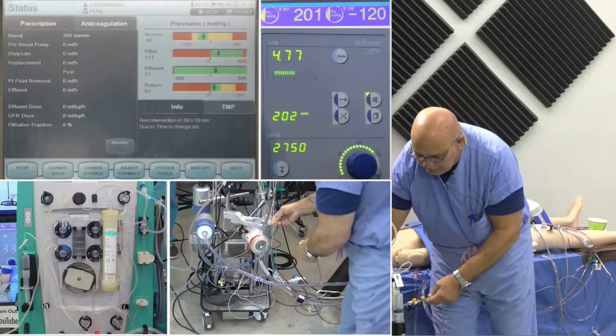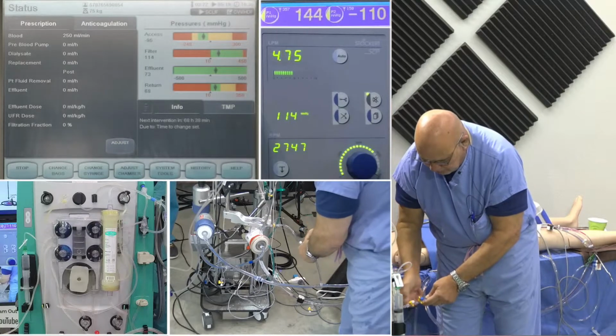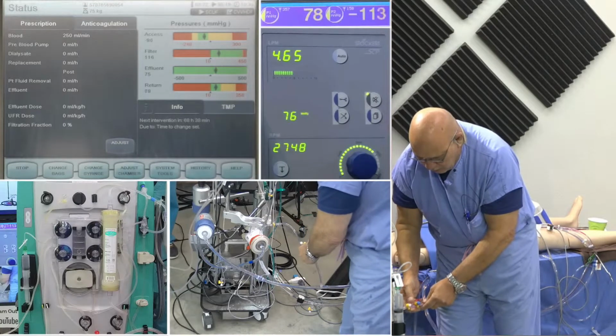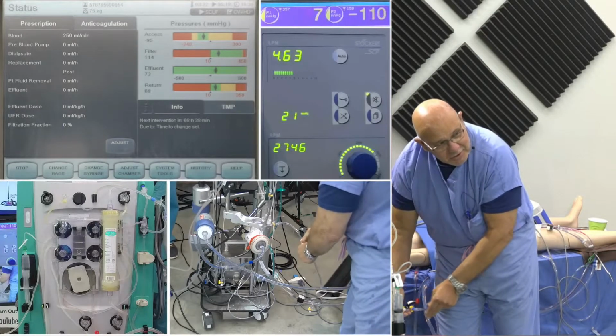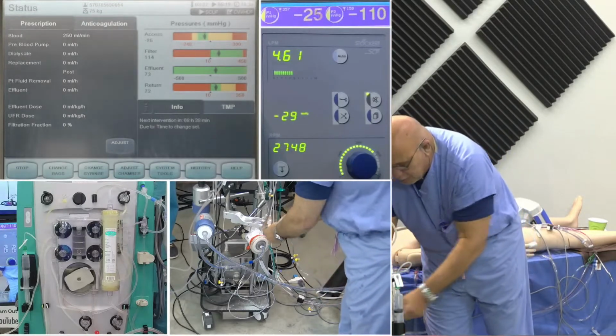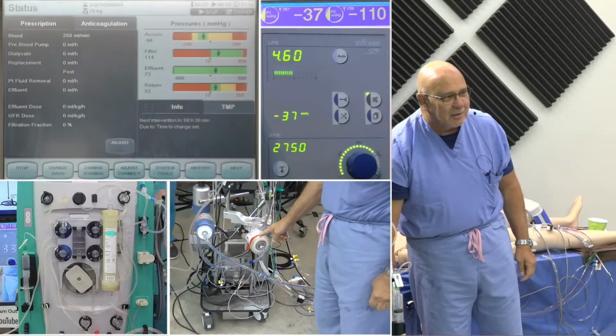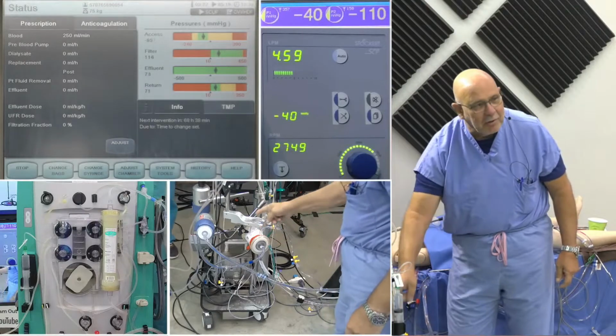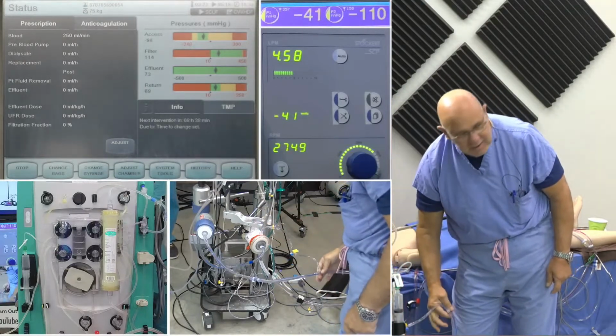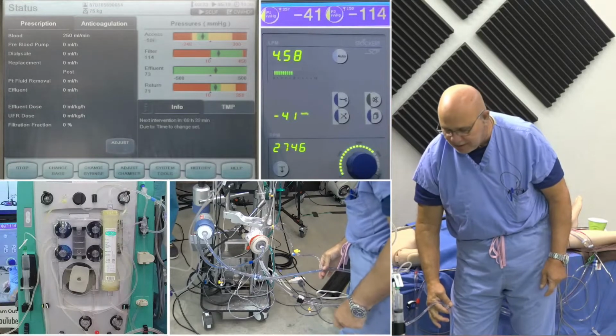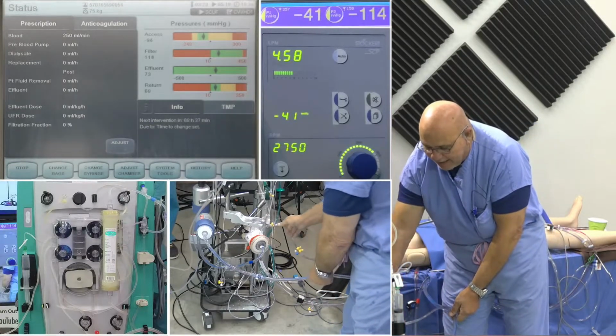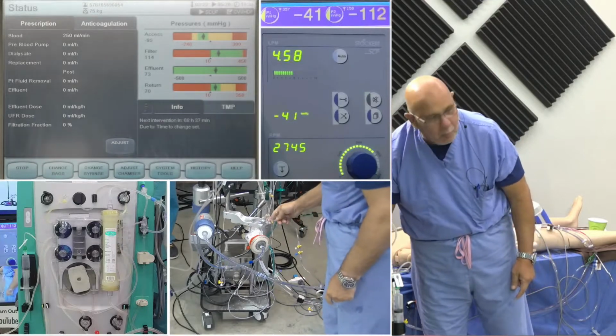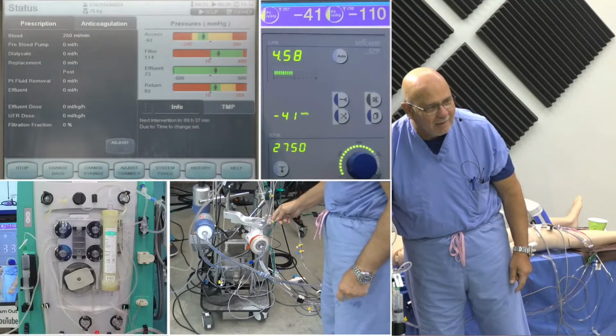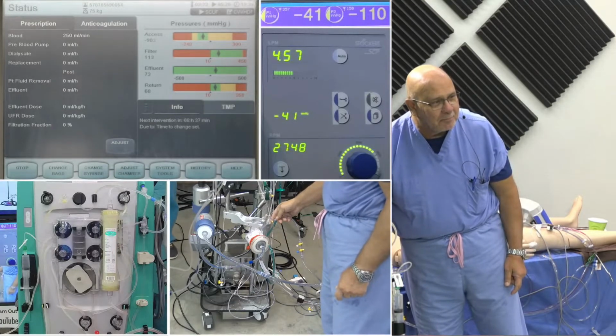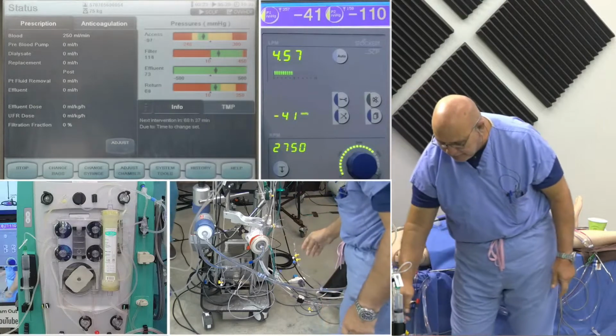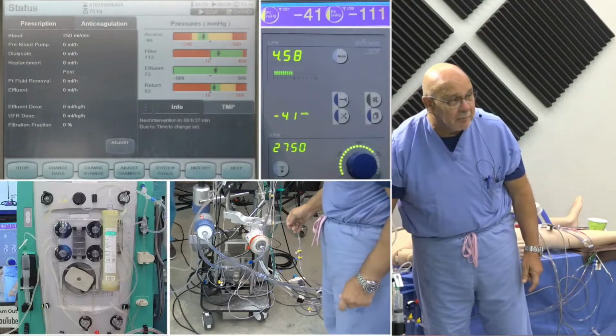If I open these lines completely, look at what happens to our return pressure. Even though that pressure coming out of here is high, the interaction of this access line, the negative pressure here, is being reflected back, and now this pressure in this port is actually lower than it's actually a negative number, which is very interesting. But that has everything to do with, now, you do, of course, create recirculation.